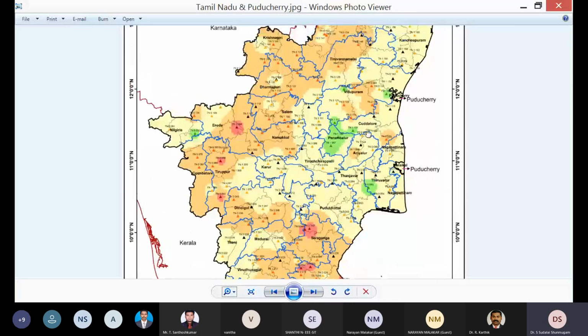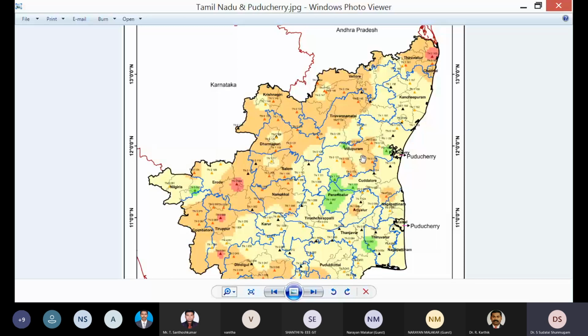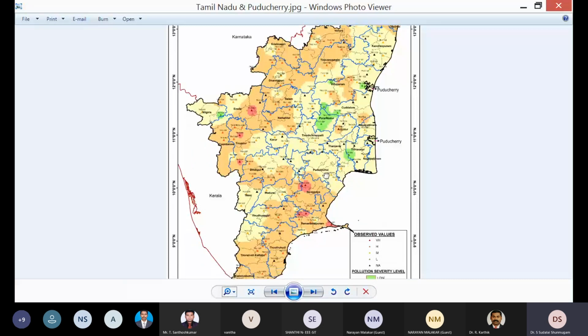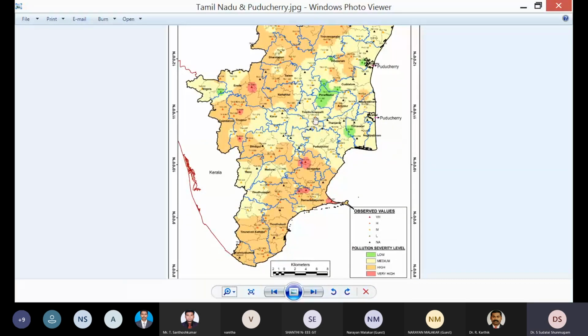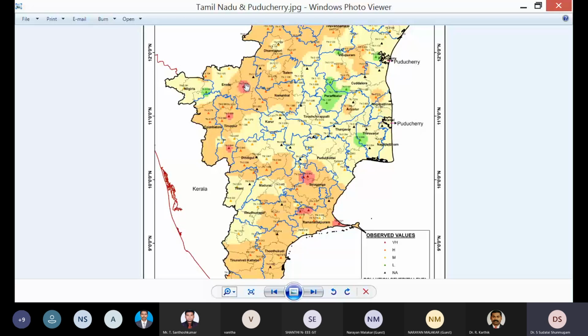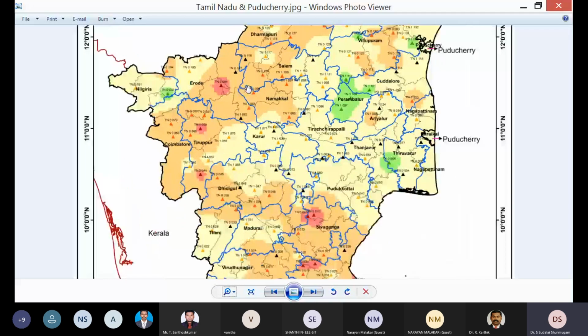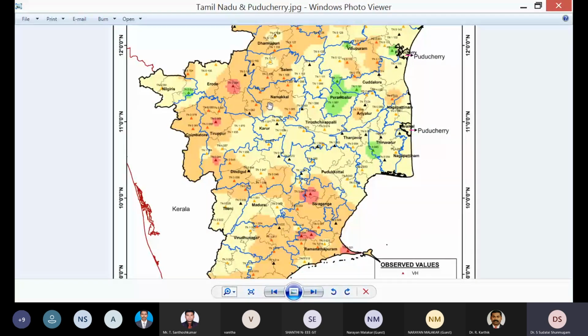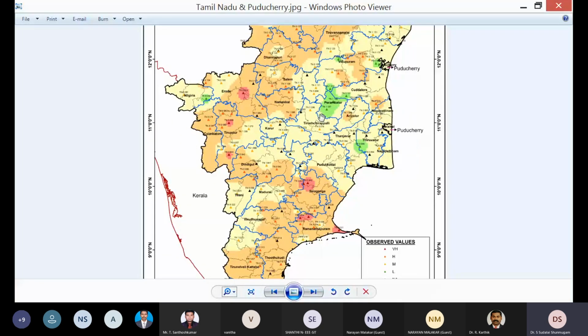This operation was carried out together by CPRI Bangalore as well as PGCIL, Gurgaon, to be precise. We can see when the transmission line is near the coast, the pollution is more. The light brown, I would say, is medium severity. The thicker one is high severity. The reddish one is very high severity. For very high severity, definitely the insulation should be taken care of immediately. And wherever high severity is there, we have to study and select the insulation accordingly, regardless of 220 kV or 400 kV line. Along with SIL, the switching impulse level, and BIL, the basic insulation level, also known as lightning impulse level, pollution severity also has to be considered, and it is right now being considered in India.